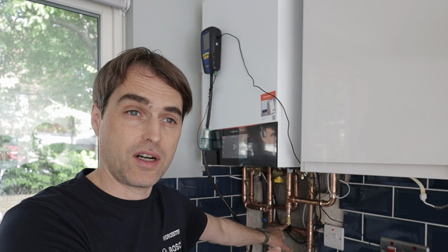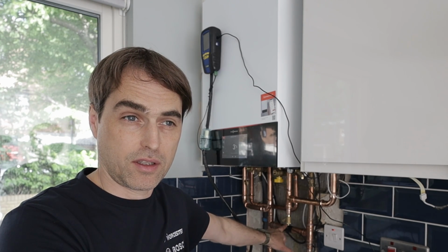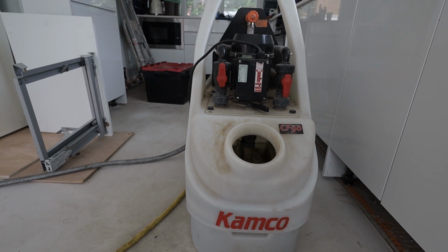Turns out I only need the mixed module, but I have to wire my pump for central heating back to the boiler, and I also have to get a 10K sensor on the closed coupled T's and tell the boiler it has a low loss header and it has a sensor. That's the only way on this W200 to make this system work. So if you ever come across it and you put closed coupled T's, you'll need a sensor and you'll have to wire it to the MMX mixed module. Took a long time and a lot of phone calls to figure that out.